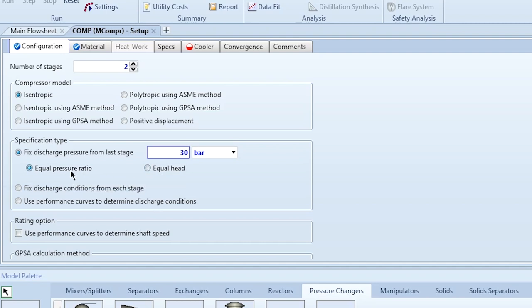There are also two distribution options: equal pressure ratio and equal head. We typically select equal pressure ratio, meaning each stage has the same compression ratio. For example, if the first stage has a ratio of 2, so does the second. If the inlet is 1 bar, the first stage outlet is 2 bar, and the second stage outlet is 4 bar — outlet divided by inlet gives the compression ratio, equal for each stage.